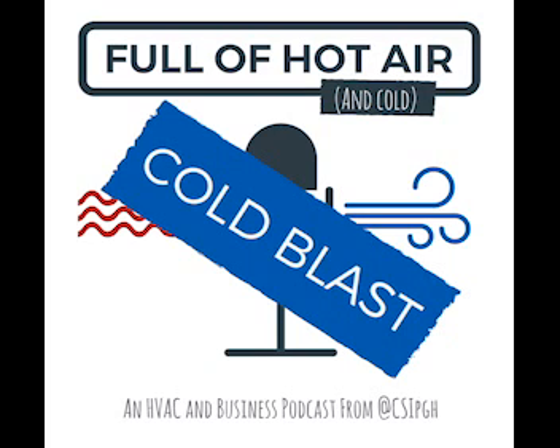If I'm reading 24 volts DC, we could forget about the outdoor unit. It's fine. It's doing what it's supposed to do. And then we could focus on the indoor unit or the wire. So right there, right off the bat, one reading, we're eliminating half the system. So at that point, if we do get to 24 volts, I'm going to do two scenarios.